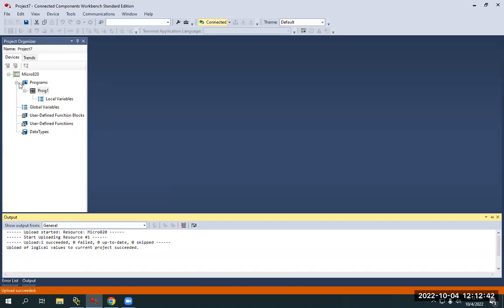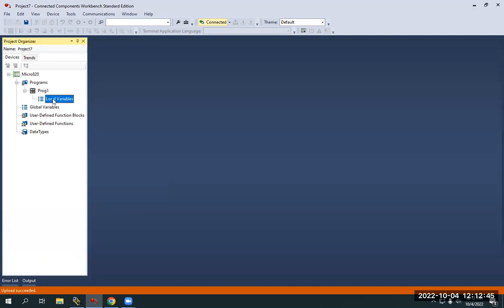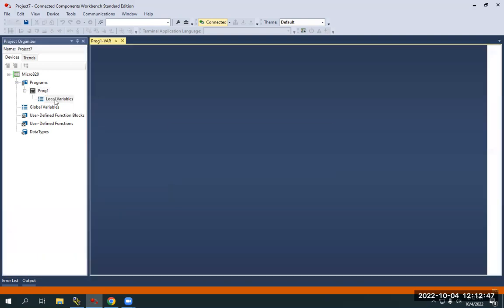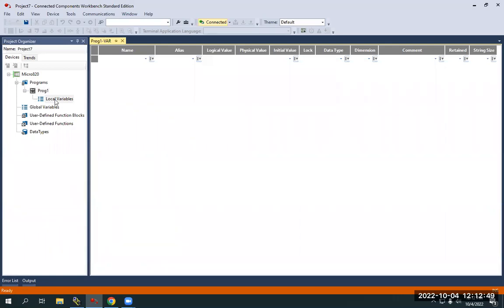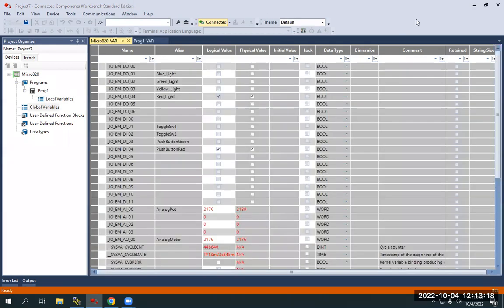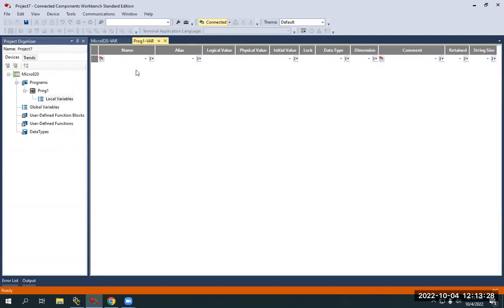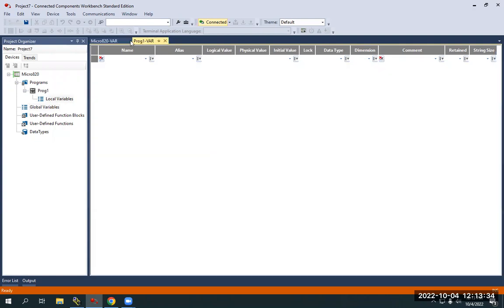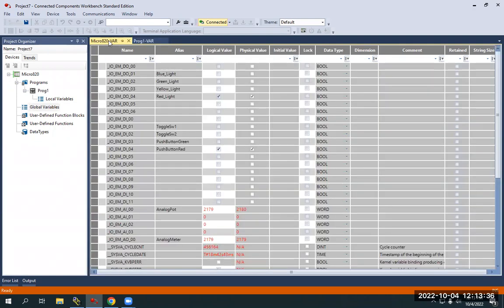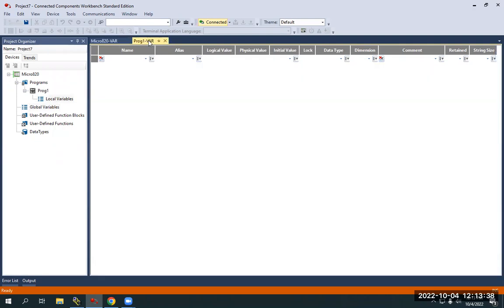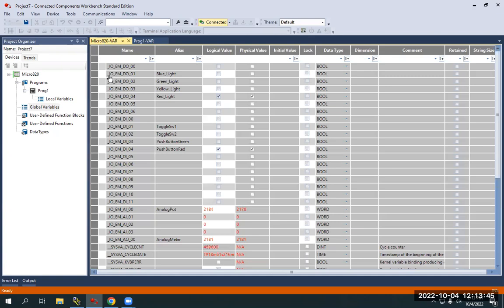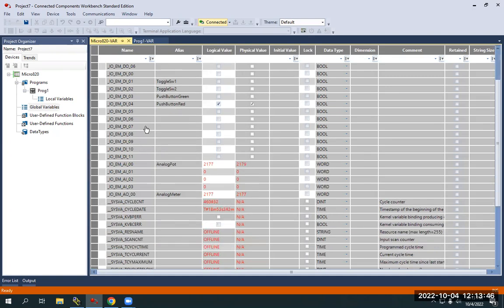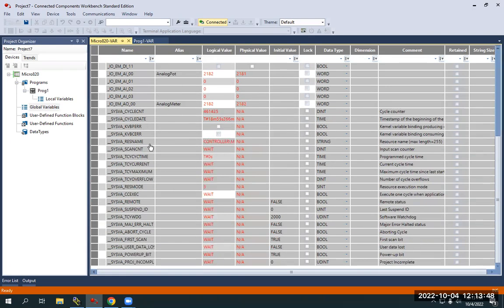So if I go into Programs, Project or Program One and then Local Variables, if I just double click on this, it's going to pull up my variable table here. And as you can see, it doesn't really have anything listed in. So what I'm going to do here is pull up the global variables, which I just did here. And the program variables should be blank. So your global variables are going to be the ones that are sort of hardwired to the PLC itself. And I can just toggle between them up here. Program ones are going to be ones you create, like your timers, your counters, and other things like that specific to the program you're building. And the Micro 820 variables are the ones that are built into the PLC.